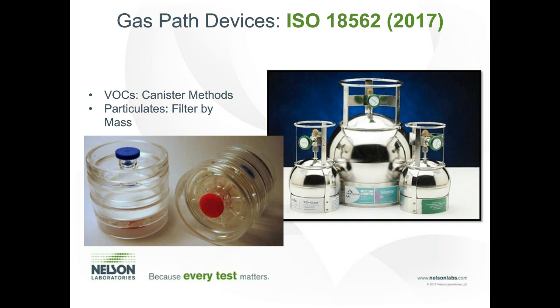I didn't want to put slides on E&L in this presentation because this is about everything that's new. And E&L, extractable leachables chemistry testing, has really become more mainstream over the past few years.